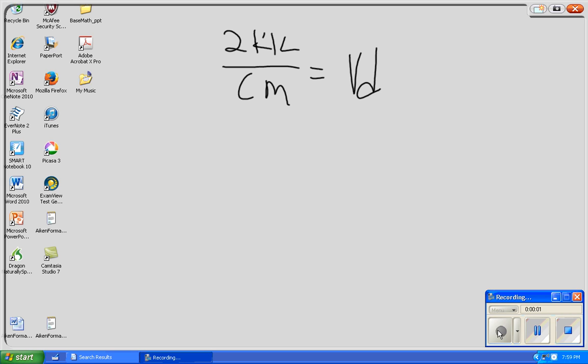We're going to talk about voltage drop today, and we're going to talk about the formula 2KIL over circular mil gives you Vd. I want you to say it with me now: 2KIL over circular mil gives you Vd. You can probably remember that from now on, after having said it four or five times.